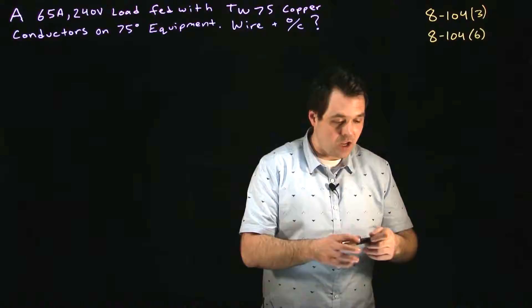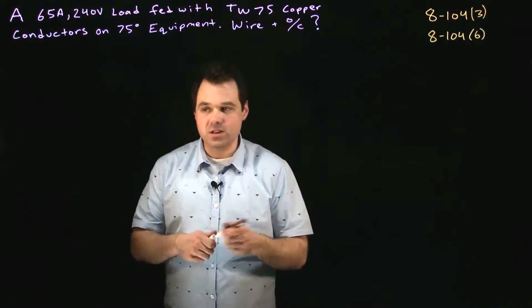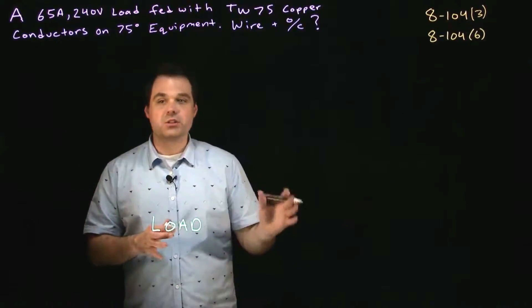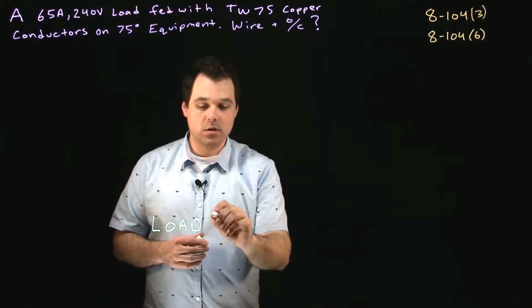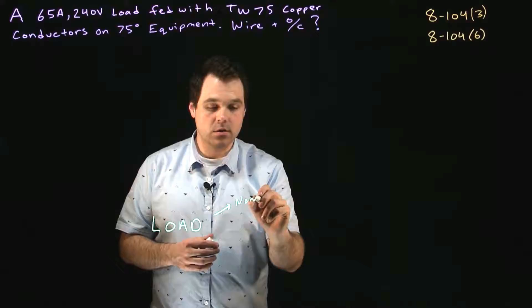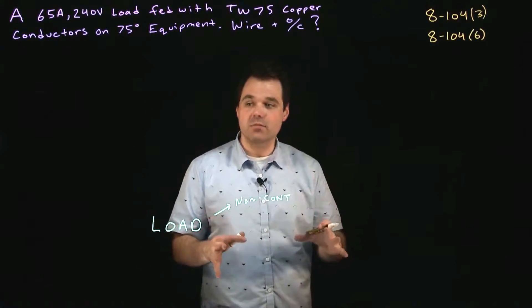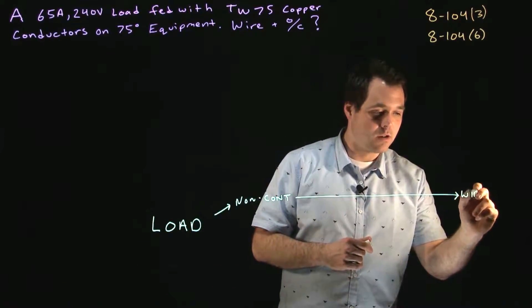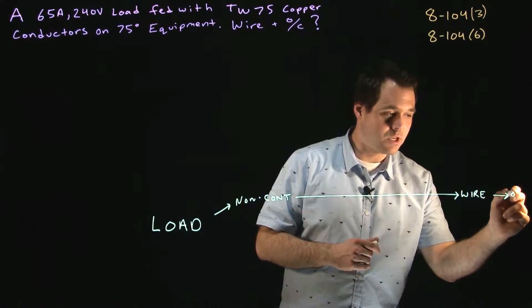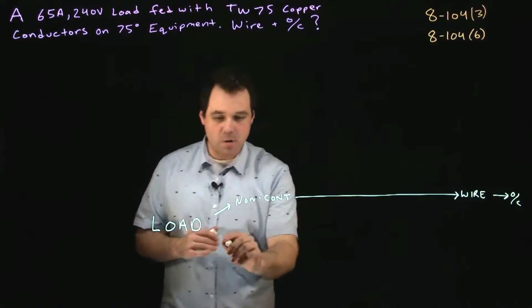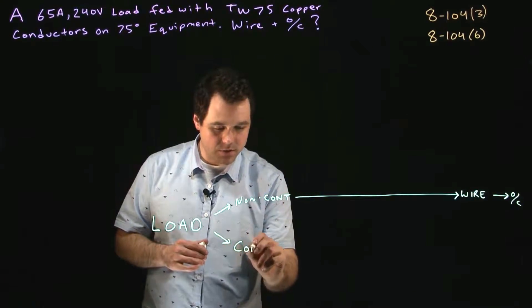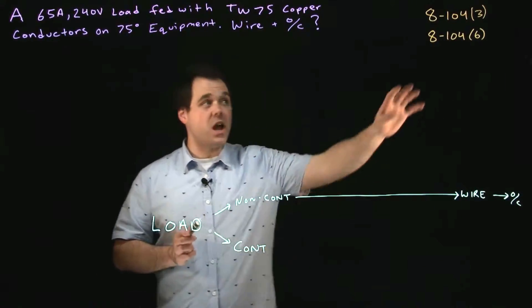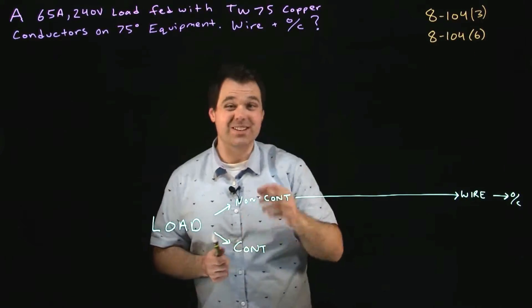So we end up with a process. We start with our load and determine: is it continuous or non-continuous? If it is non-continuous, it's easy — the load isn't running all the time, it's not producing a lot of heat, so we simply size a wire and size an overcurrent device. However, if we have a continuous load — and remember, 8104 Subrule 3 tells us all loads shall be deemed continuous unless told otherwise — the process is different.